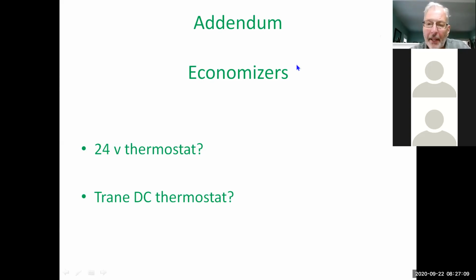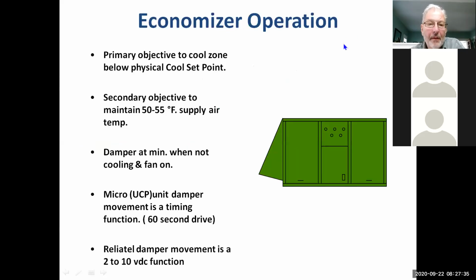So I'm going to talk a little bit about economizers because we're in that season where economizers are going to be the big question right now. On the Trane American Standard units, we have two different ways of operating our economizers. If it's a Reliatel system, we can use a 24-volt thermostat or a Trane DC thermostat, and it makes a difference in the way the economizer operates. So what is an economizer? What are we looking at when we put an economizer on a system?